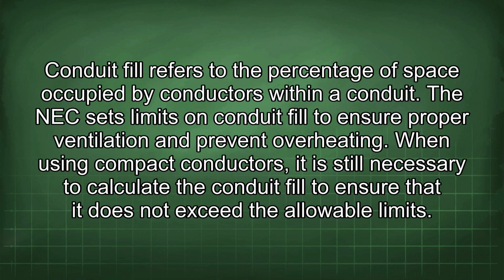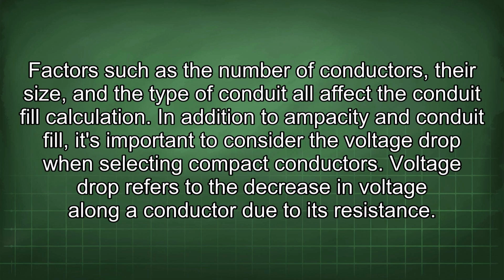Conduit fill refers to the percentage of space occupied by conductors within a conduit. The NEC sets limits on conduit fill to ensure proper ventilation and prevent overheating. When using compact conductors, it is still necessary to calculate the conduit fill to ensure that it does not exceed the allowable limits. Factors such as the number of conductors, their size, and the type of conduit all affect the conduit fill calculation.